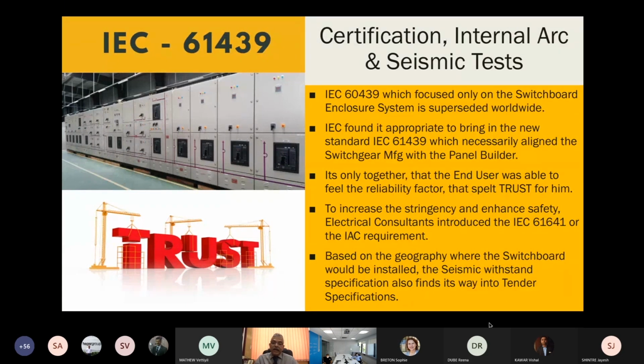Now, as things evolved and as this need for reliability and safety increased, the IEC Council sat together and they evolved the IEC 61439 standard. And now the significant difference between 60439 and 61439 is that we could no longer take an enclosure and busbar system alone for type testing. We had to take the switchgear mounted inside the enclosure, and the switchgear was also tested. 13 tests were defined as what is important for the reliability and trust to be built into the whole system. And that is what brought about the 61439 standards.